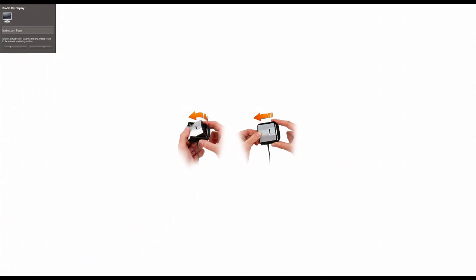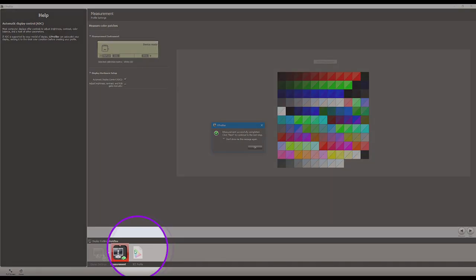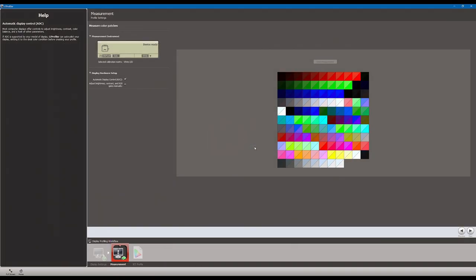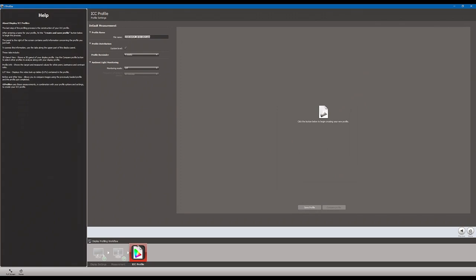Now we're at the final stage of the calibration where it wants me to essentially remove the calibrator from the monitor, flip the shield over and lock it in in front of the sensor, and then set the calibrator on my desk so that it can do an ambient light reading of the room. This is the final most crucial step where it's going to read all the light in the room and then balance that out to the profile that it just created. So to be able to do that, I'm going to go ahead and hit next. And it says measurement successfully completed. Click next to continue to the next step. And this is where we're going to now move into the final stage of the workflow here where we create the ICC profile. So I'm going to go ahead and hit OK and then come down here and hit next as it's instructing me to do.